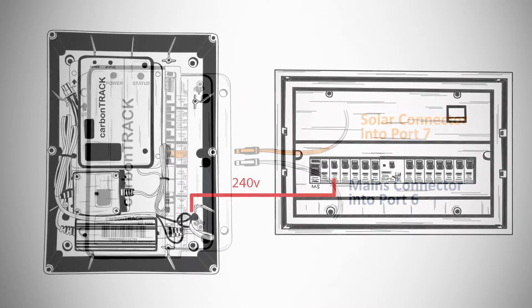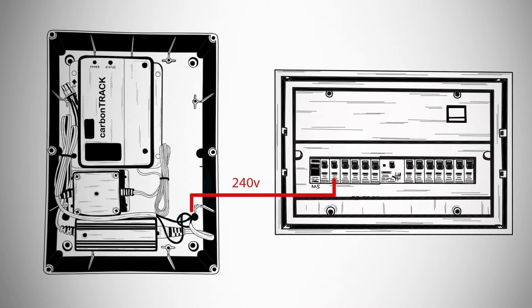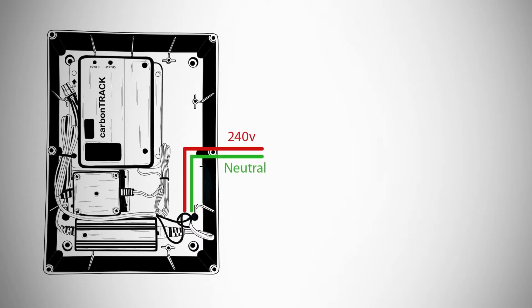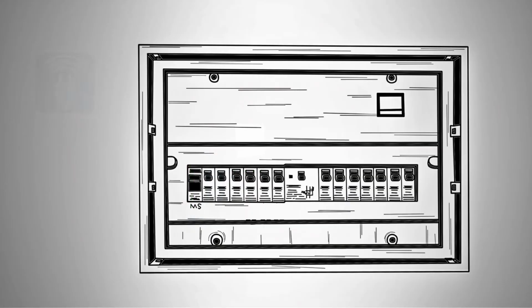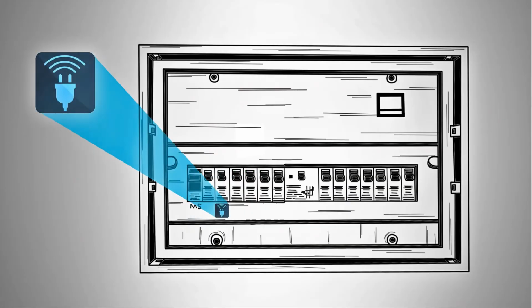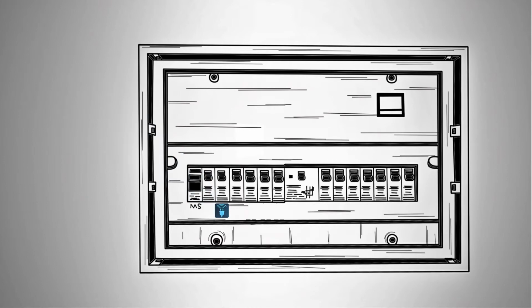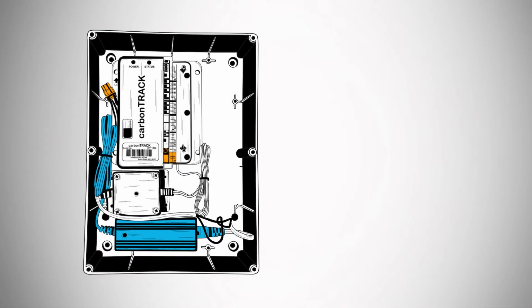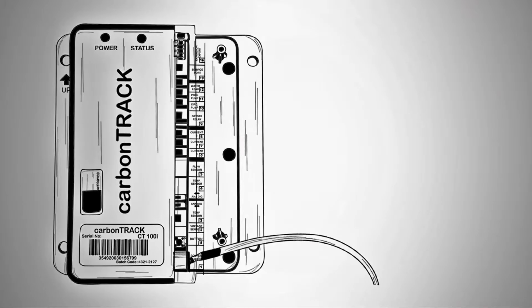To power the CT100i, run 240 volts from a suitable breaker into the distribution board. Connect neutral and terminate earth. Next, stick a carbonTRACK label on the circuit breaker from where you got 240 volts. Next, plug the power supply connector into port number 1 of the CT100i. Switch on circuit breaker. The green light on the unit should come on solid, and the red light should blink a few times and then go off.